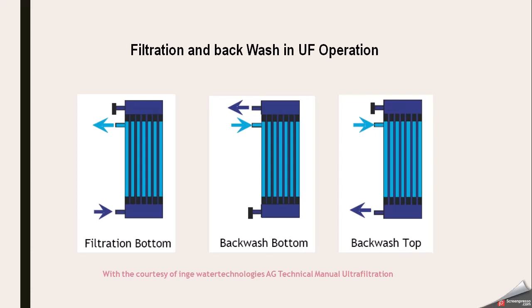In normal filtration, water goes from the bottom, moves from outside the membrane, and purified water comes inside — we get permeate. In backwash bottom mode, the bottom valve is closed; water enters from the permeate path, becomes pressurized, and flows from inside to outside going upward to clean the membrane. In backwash top mode, the top valve is closed and water still enters from the permeate path, exiting as reject from the bottom.